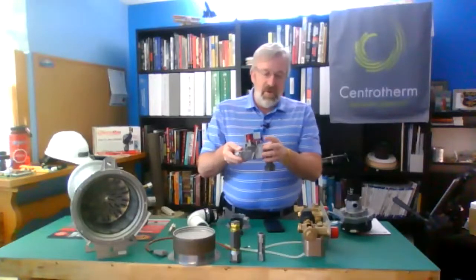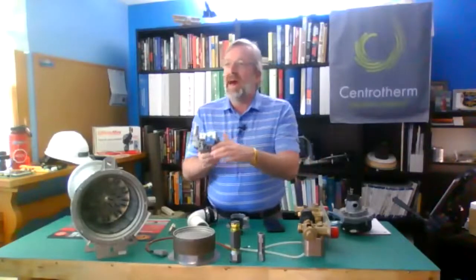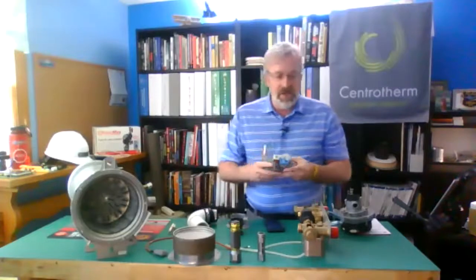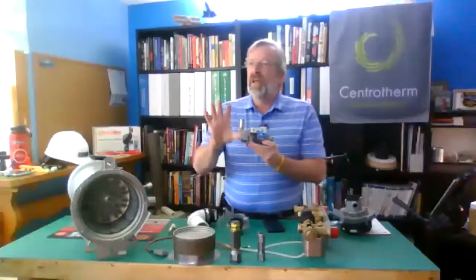So what I want to do is put my gas pressure manometer on this side right here. The reason I want to do that is I want to make sure that I have gas, my gas valve opens, and I have enough gas. So it's really a couple of questions. Put my manometer out here. For today's conversation, we're going to discuss it as though it's natural gas. The numbers will be natural gas related. So I want to be between 4 and 14 inches natural gas. To put my manometer on here, I've got 8 inches of gas while it's static. My boiler's off. Perfect. I have the appropriate gas pressure.